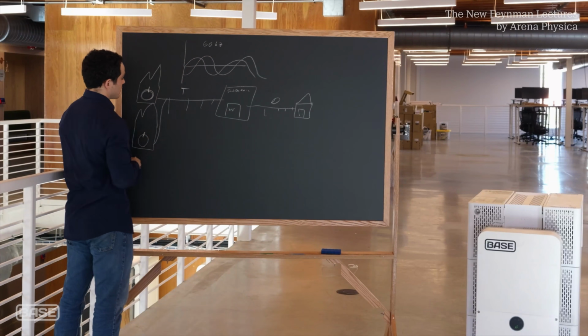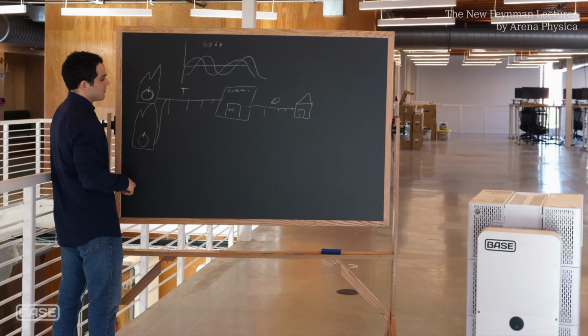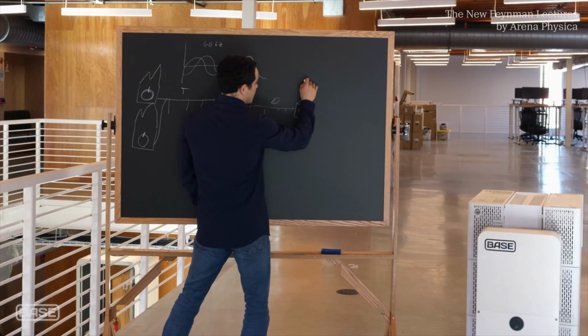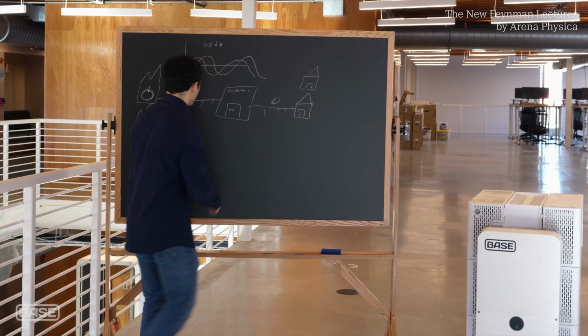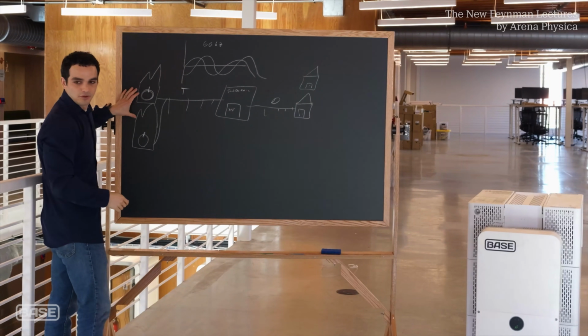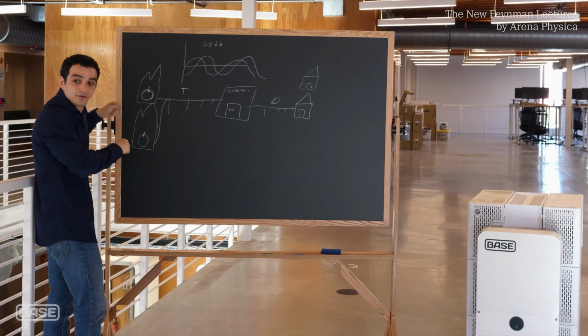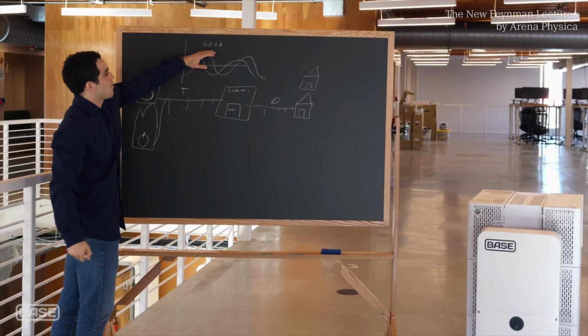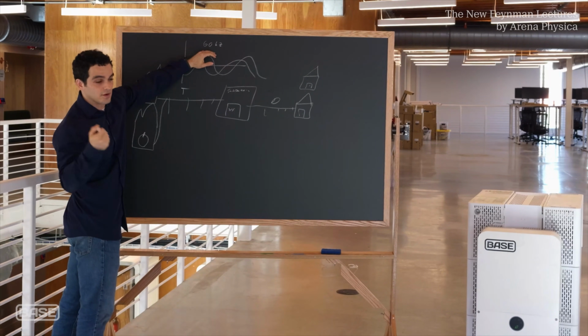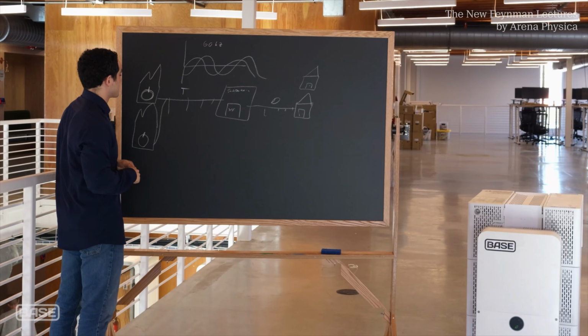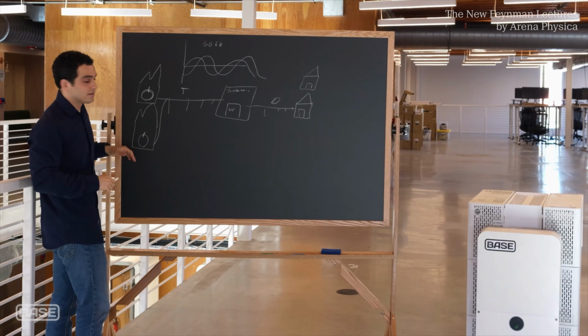The 60 hertz number is very important, because as you add more load—more homes, people turning on their ACs, whatever—it puts more load on these generators, and they want to slow down a bit. So how close you are to 60 hertz on the grid is very closely monitored as an indicator of how much load there is on the grid.